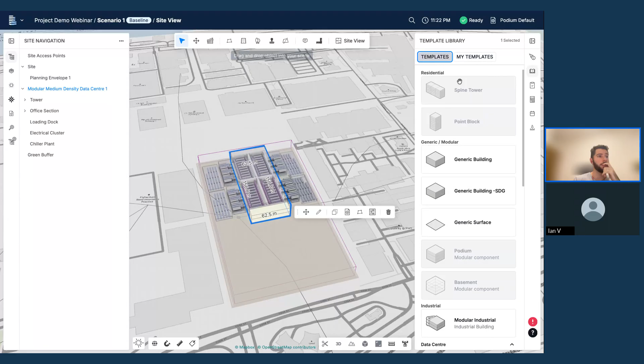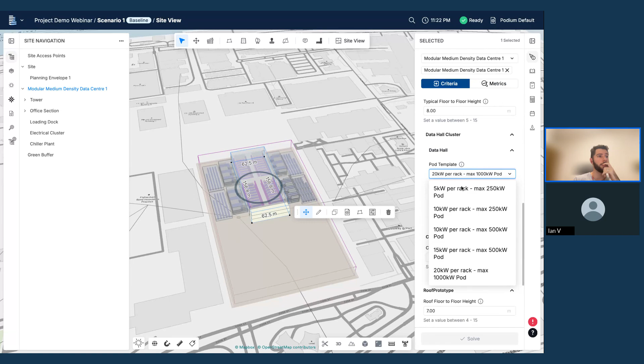Besides that, I changed a couple of criteria, but I can change way more. In this case, I could say I don't want 20 kilowatt per rack, I want only 10 kilowatt per rack. The automation runs again, the metrics are recomputed, and now the building went from 80 megawatts down to only 32 megawatts. This allows really quick iteration and quick studies on your site.